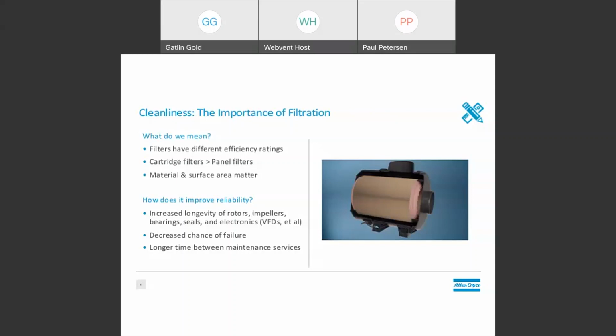Cartridge filters, like we have pictured here on this slide, have an elastomer seal at both ends that form an interference fit within the housing. Particles cannot bypass a cartridge filter. Panel filters, like we typically see in our home HVAC systems, right? We're all familiar. These work well under constant vacuum, right? When we're pulling a vacuum through that filter, nothing can get through it.